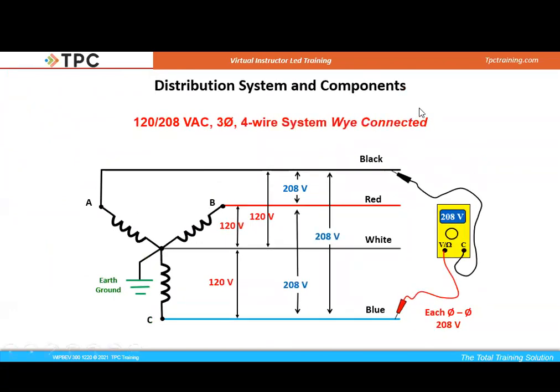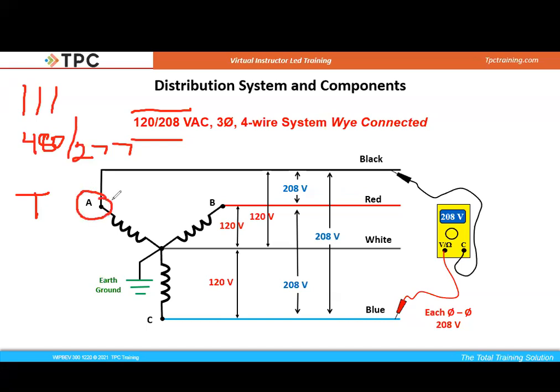We could also have this system, which is very similar, only just a little bit lower voltage. So on this one is going to be 120, and so let's say that the utility comes in with 480, and that's all they're going to give us, 480, 277. So somewhere in my facility, I would have a transformer to change that down to my 120, 208. But this works very similar to the other system because from my energized conductors on the outside, I am always going to have the higher voltage, which in this case would be 208.